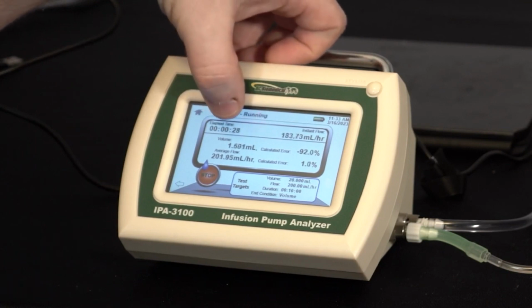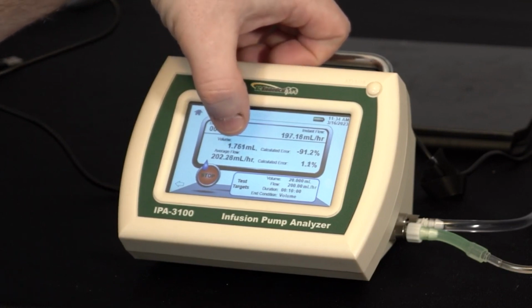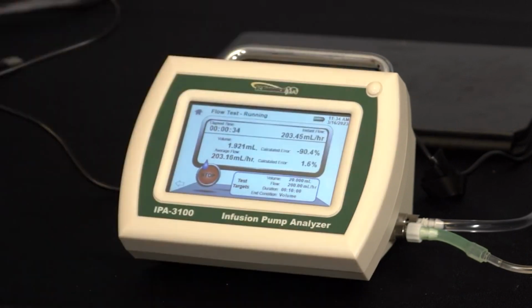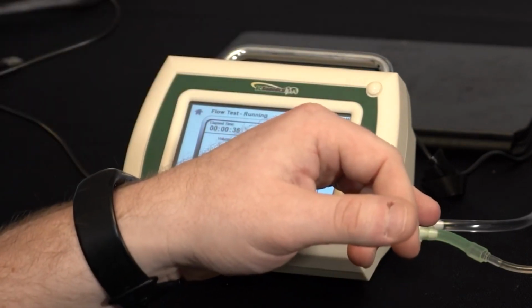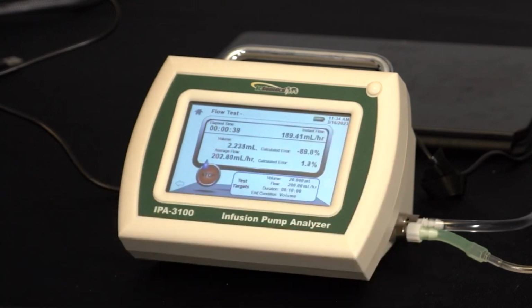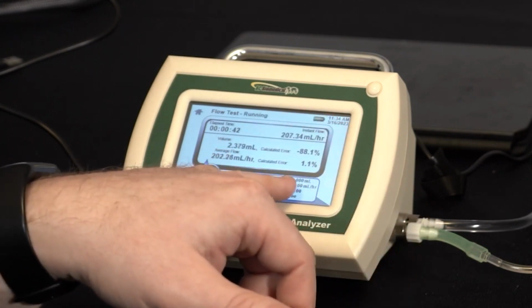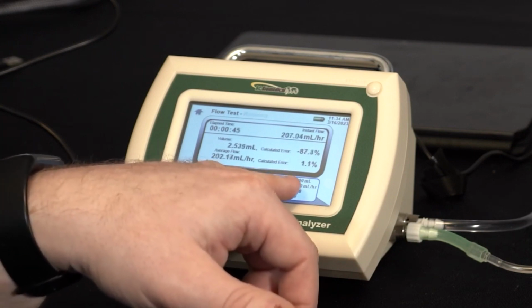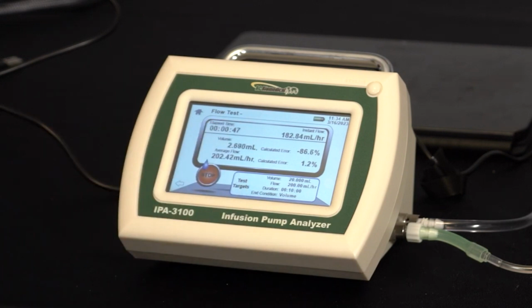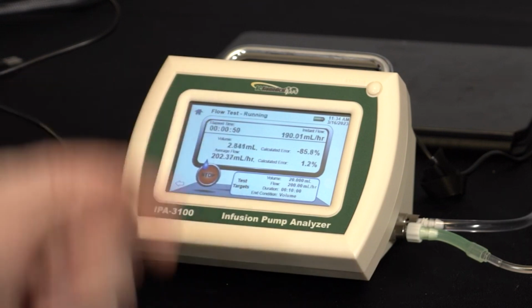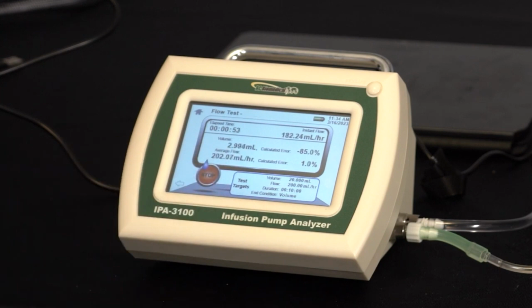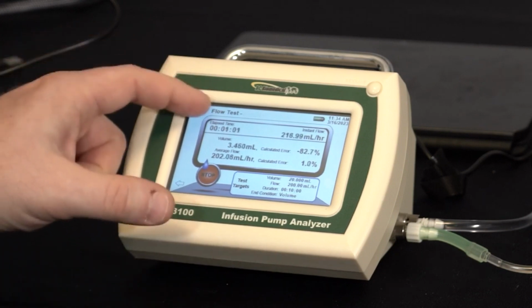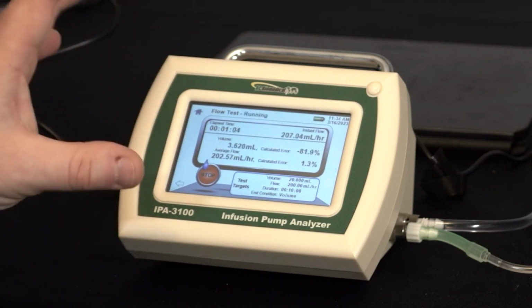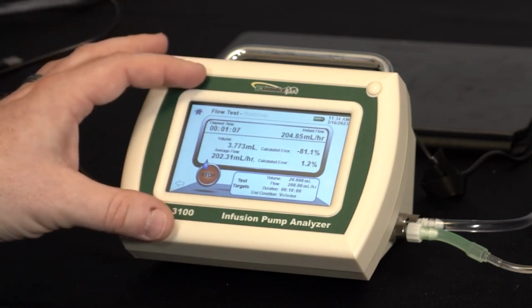We've got an accumulated time at the top, and then our measured volume and average flow shown in the middle of the screen. Now, the calculated error looks really large right now, again, because it's using the configuration that I had initially. I told it I was going to do a 20 milliliter dispense, and I'm not anywhere near that right now. So once we get to the end of the test, that's when we can compare the volume. But the average flow runs continuously as the test is running. Now we can also see that we can't get out of the screen because the test is active. So really, when you're running the test, you need to stay in the screen.